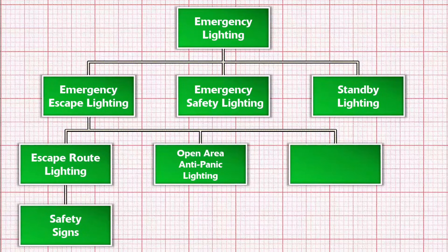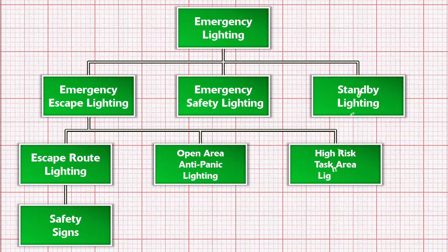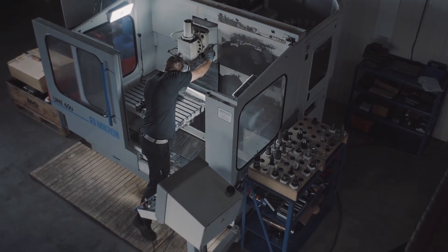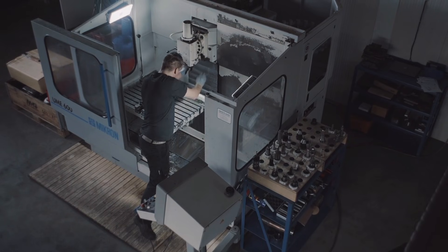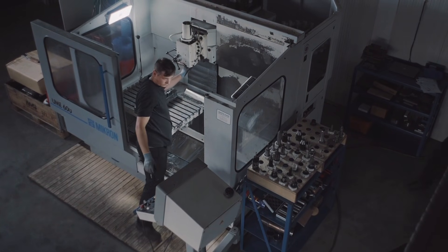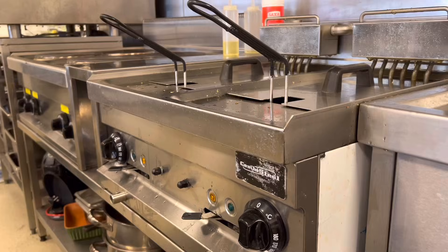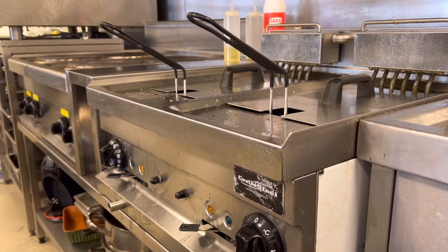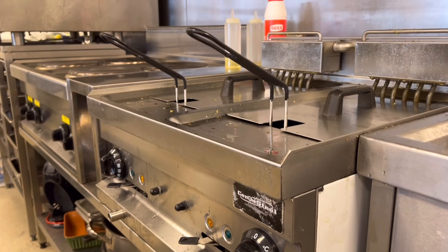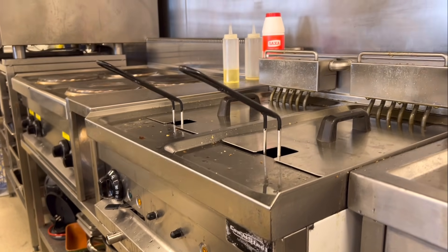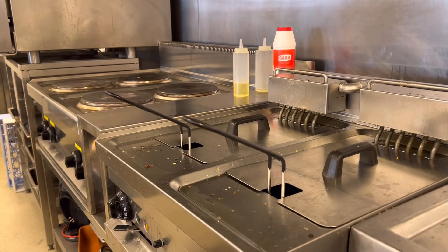The third category of emergency escape lighting is high risk task area lighting. This is required in areas to protect people engaged in potentially dangerous processes or situations who need sufficient light to shut things down safely. A good example is an industrial kitchen where people are working with sharp knives, boiling hot fluids, and naked flames.